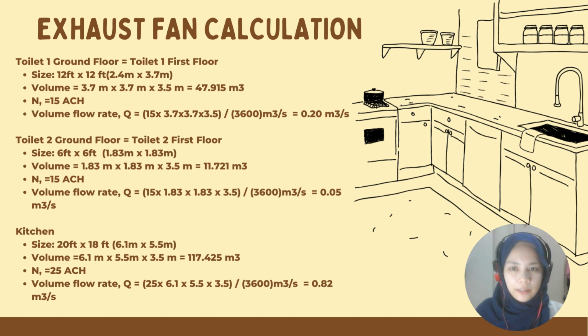Exhaust fan calculation. First place is toilet 1. Toilet 1 size is 12 feet times 12 feet. Volume is 47.915 cubic meters and is 15 ACH. Our volume flow rate Q is 0.20 cubic meters per second. And second place is toilet 2. Size 6 feet times 6 feet. Volume is 11.721 cubic meters and is 15 ACH. Volume flow rate Q is 0.05 cubic meters per second.